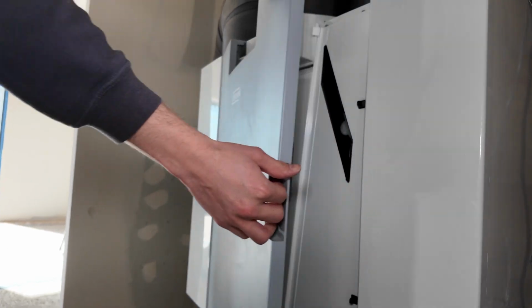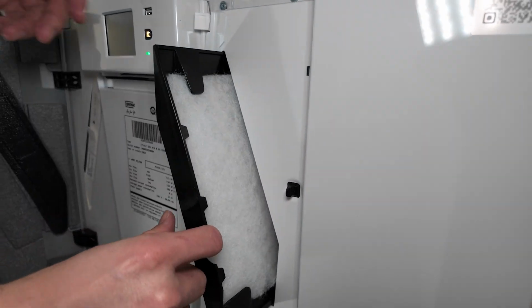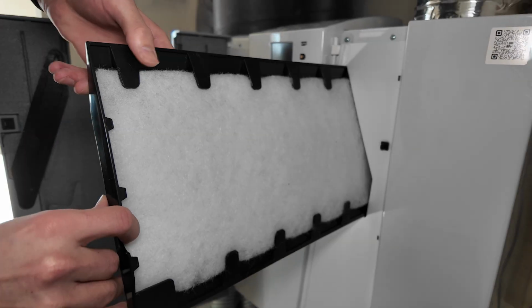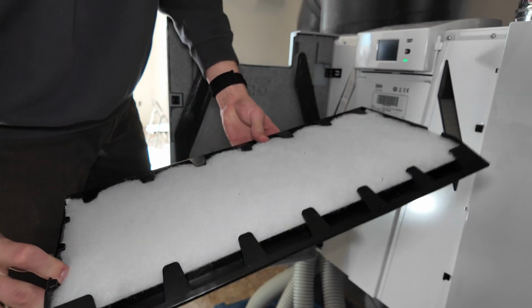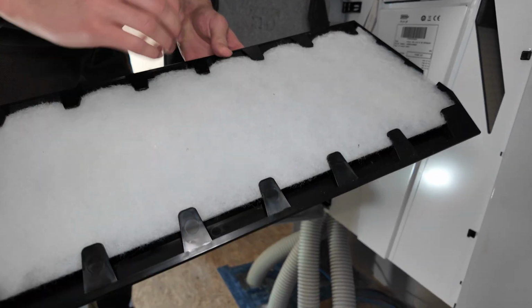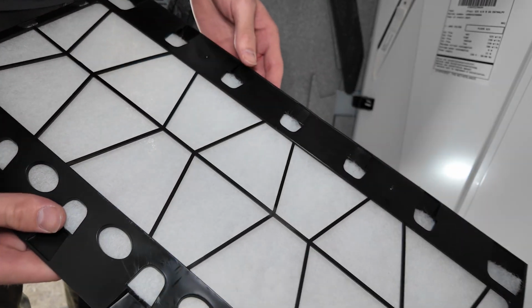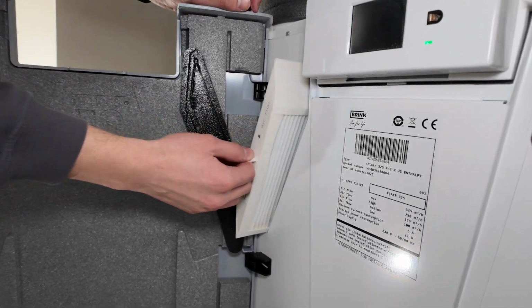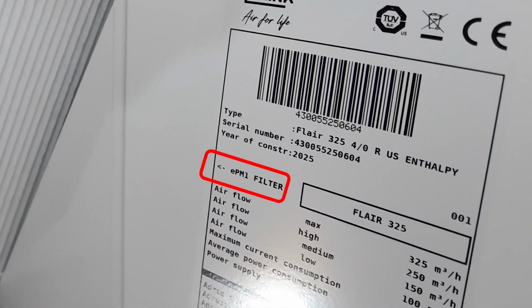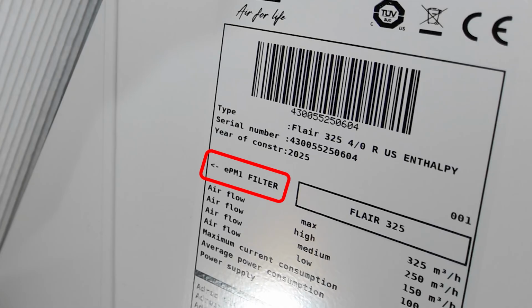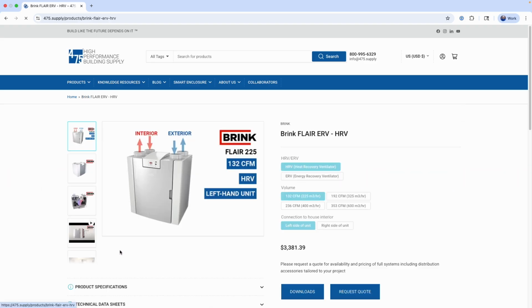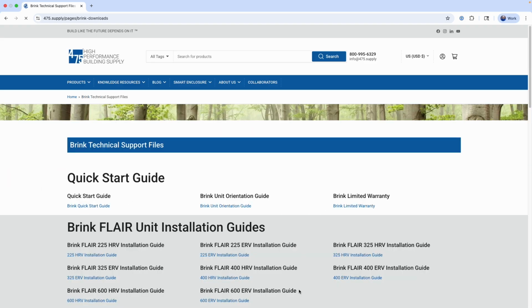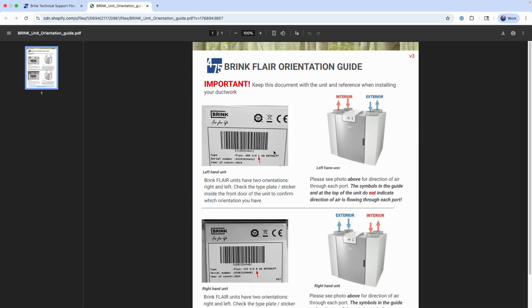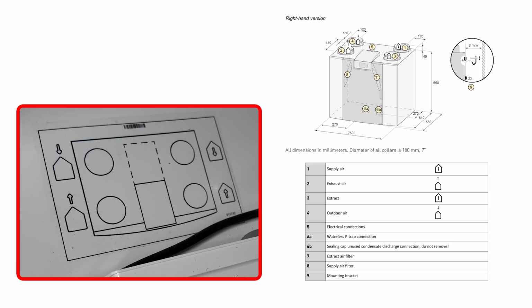The agent should also inspect the filters and replace them if they're dirty. Check to make sure that all appropriate filters are installed in the correct slots. The MERV 13 filter should be placed on the side of the outside air ducts. For additional reference, see the Brink orientation guide on our website. We always recommend referencing this guide as the symbols on top of the unit don't include a legend.